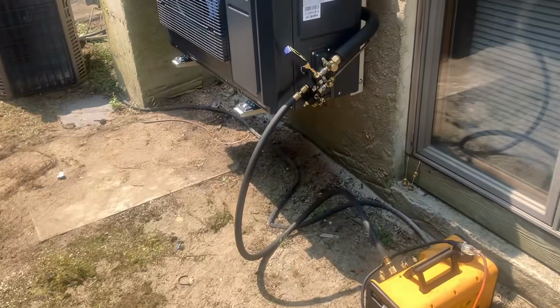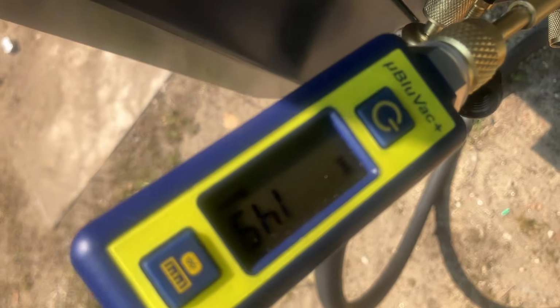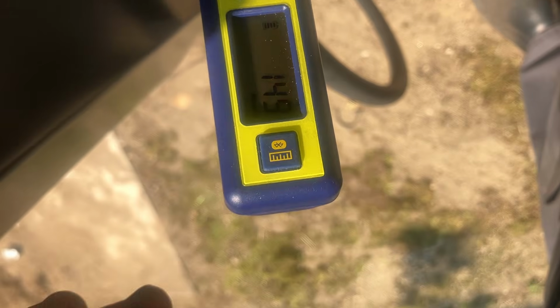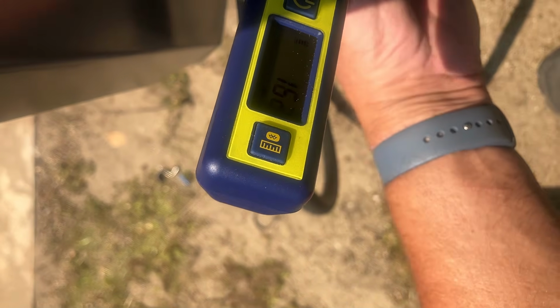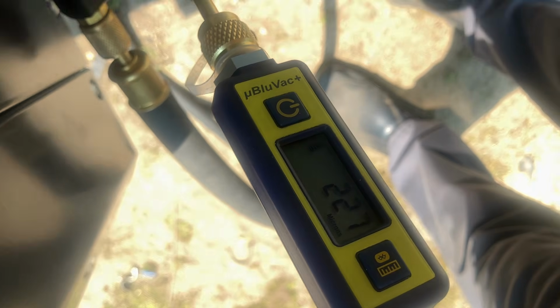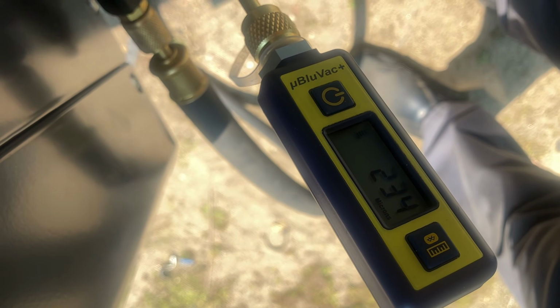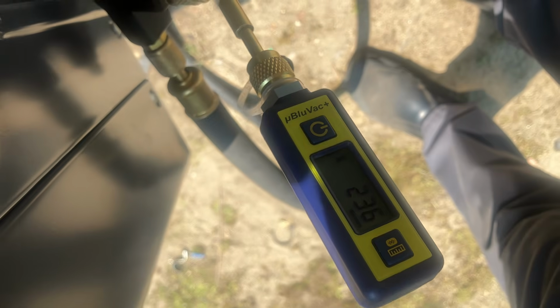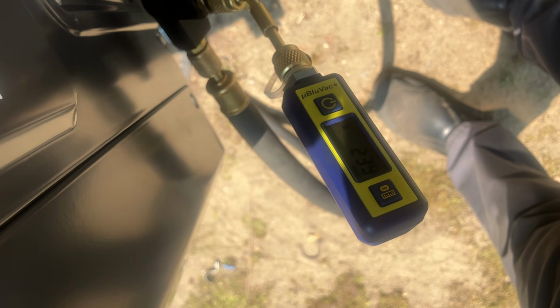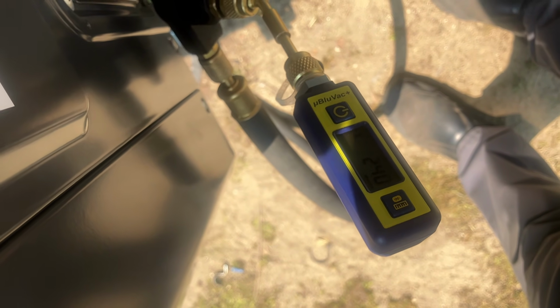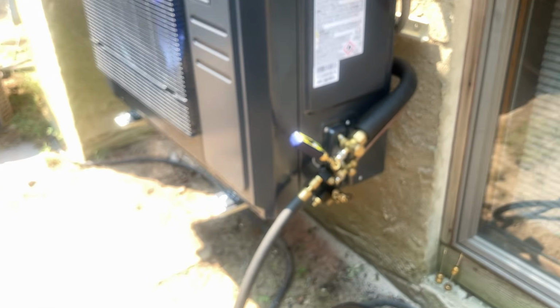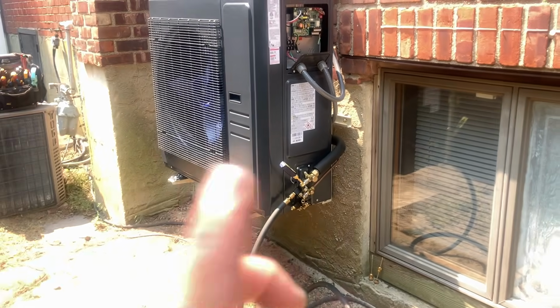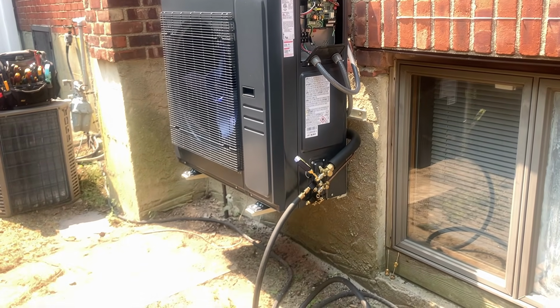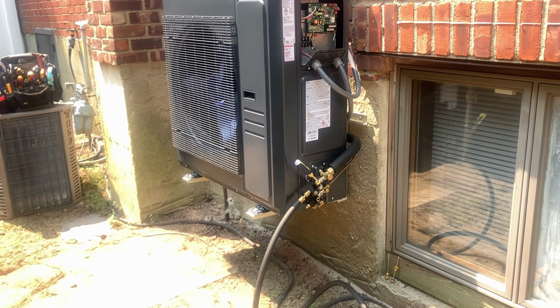All right, it is 11:45. We are at 149 microns. Let's close this valve. 227, 230, 231, 234, 235, 239, 240. Let's let this sit for a minute. We do not want that to start creeping up to 500. We want to make sure that micron gauge doesn't go up too much, because that'll prove there's hardly any moisture left in the system.